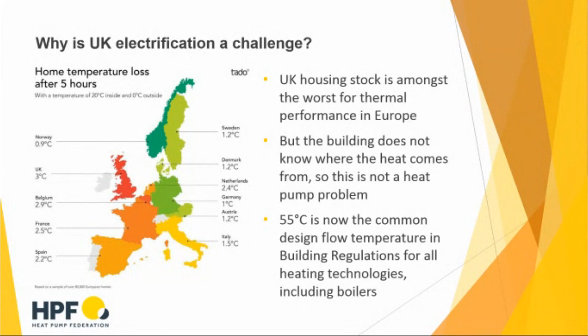But the key to remember is that the building doesn't know where the heat's coming from. So this isn't actually a heat pump problem, it's a heating system problem. The fact that we now have 55 degrees centigrade as the common design flow temperature in building regulations for all heating technologies, including condensing boilers, which are a low temperature heating device, is good news in this respect.